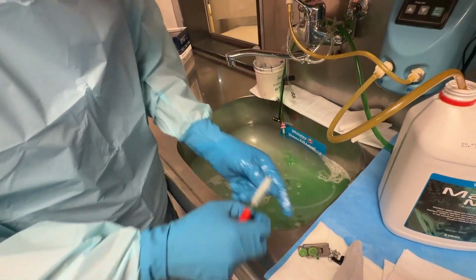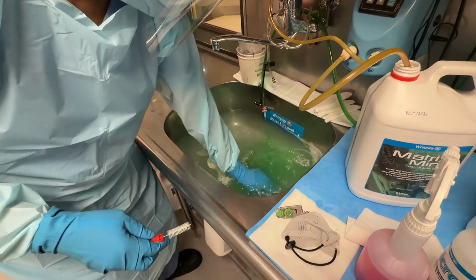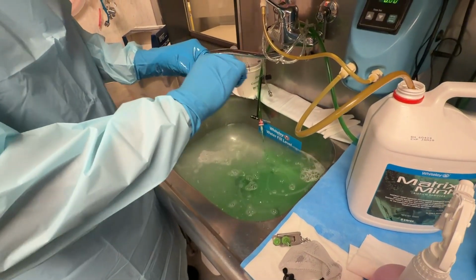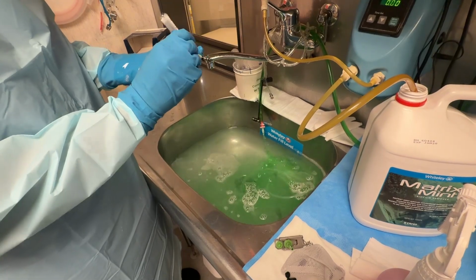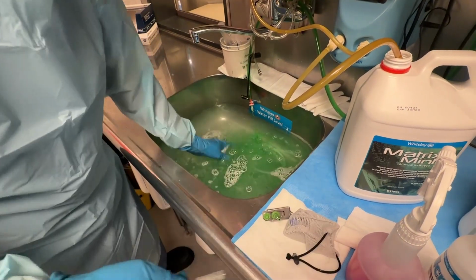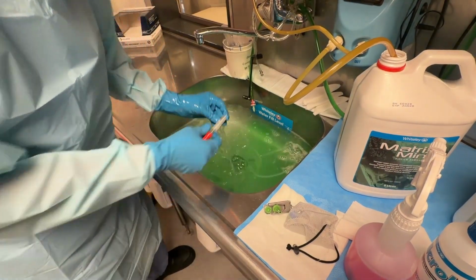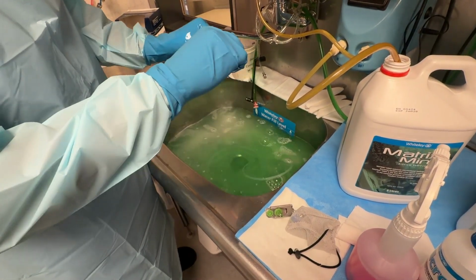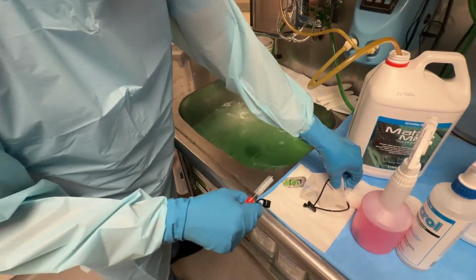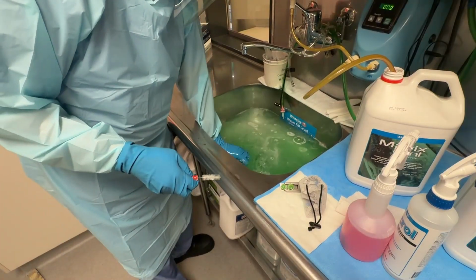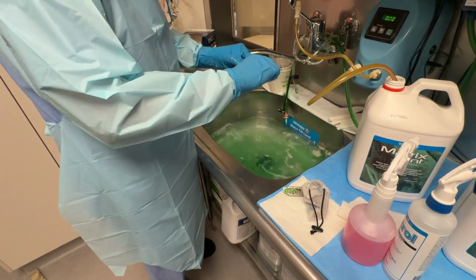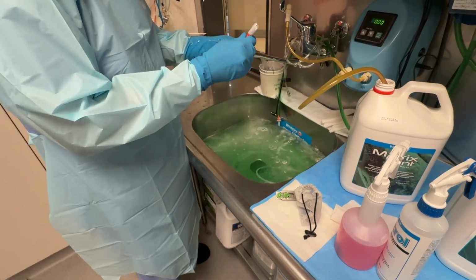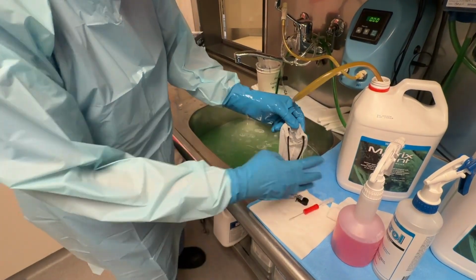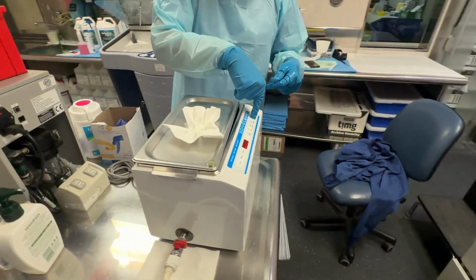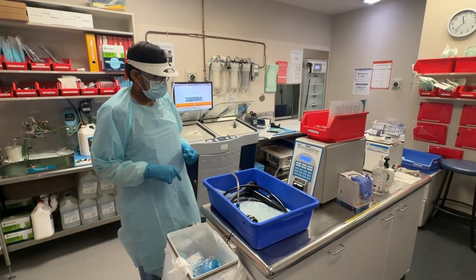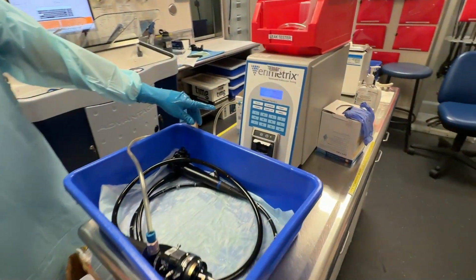Once the water is filled to a particular level, we will start filling the sink with the Matrix. Matrix is a non-enzymatic detergent and a biofilm remover, and we will check the buttons for any debris that has been trapped inside the springs or any connections, any holes. We will put the two buttons inside the button bag, and the tubings are also flushed with water to avoid any debris trapped inside the tubing. And we will put the tubings and buttons in the ultrasonic to loosen the debris.